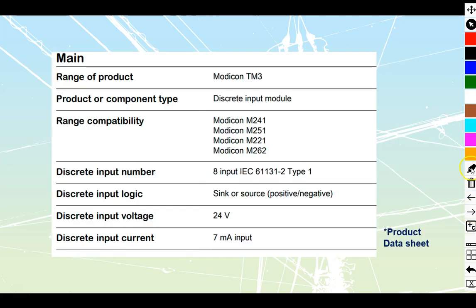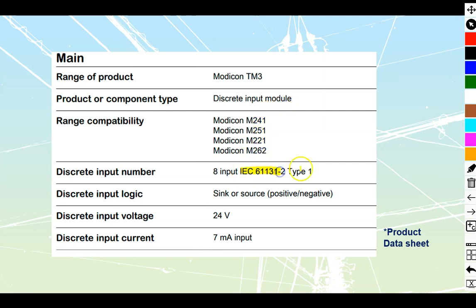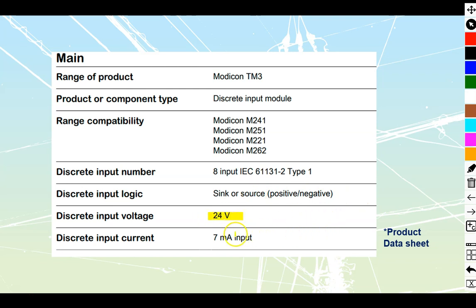Okay, let's take a look at our manufacturer's data sheets. First thing that we're going to note is that this thing is going to be applicable across pretty much the entire Modicon family, everywhere from the 241, 221, 251, and 262. It is going to be 61131 compatible. That's our main PLC programming guideline. And we can use it as syncing or sourcing. The previous video showed it as being a syncing. Now we're going to try it as a sourcing. It's got a nominal voltage of 24 volts, and each of my inputs takes no more than 7 milliamps. So even if you've got a 32-input card, you're not going to be running more than a quarter of an amp, 250 milliamps, into it at any time. They're very, very low-powered.